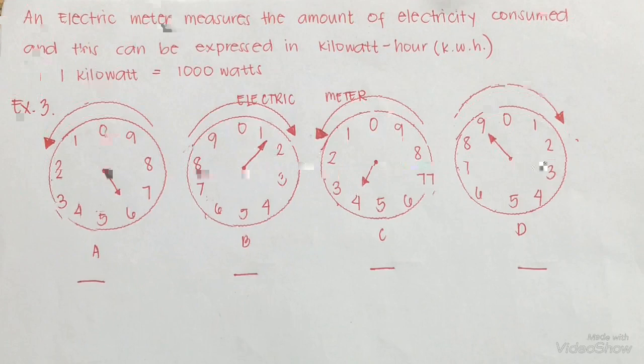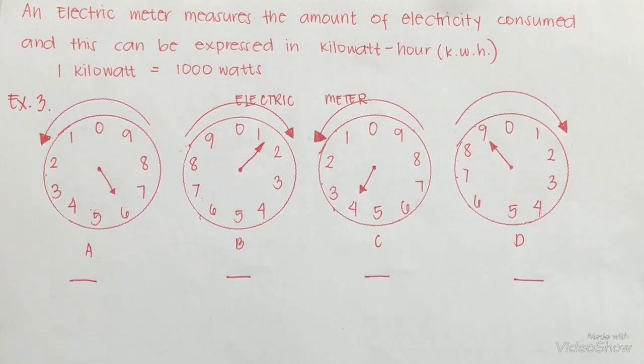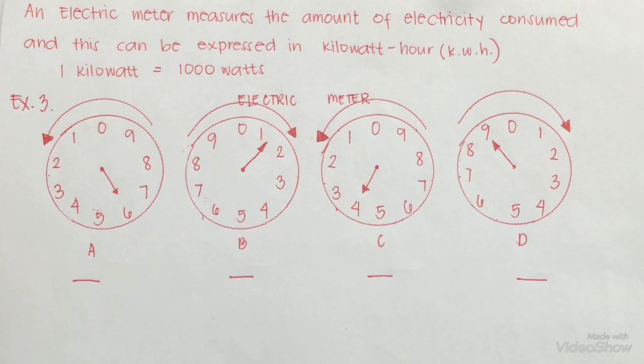An electric meter has four dials. The pointer of each dial moves 10 times as fast as the dial on the left, and the pointers of dials next to each other move in opposite directions. The pointers of dials B and D move clockwise, while dials A and C move counterclockwise. If the pointer is between two numbers, record the smaller number. The reading of the electric meter shown above is 6149 kilowatt hours.